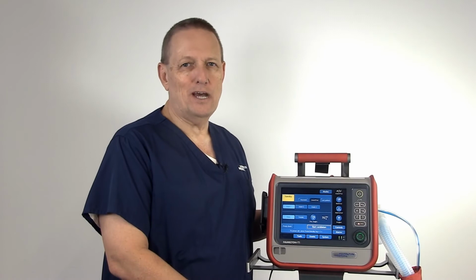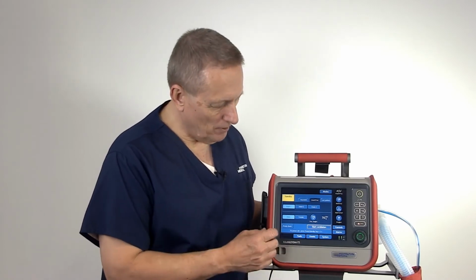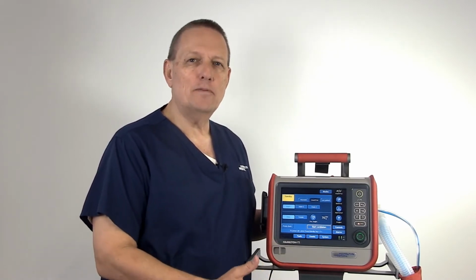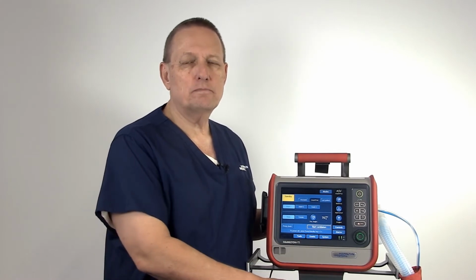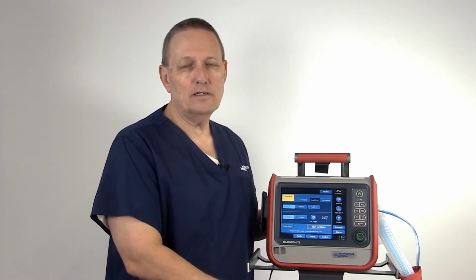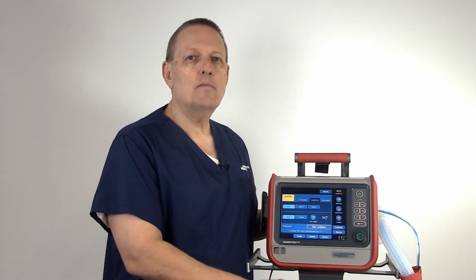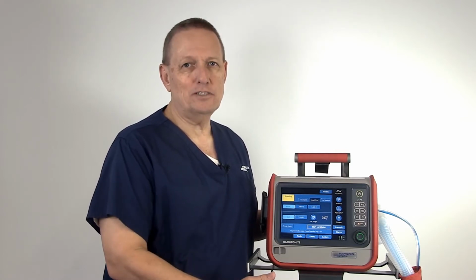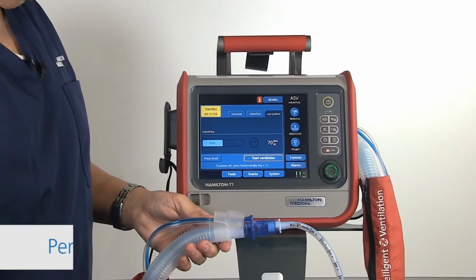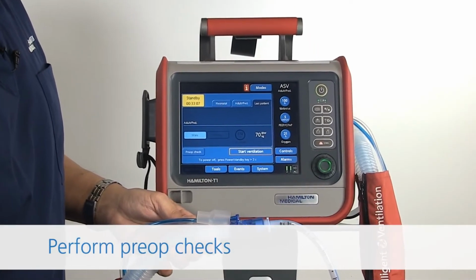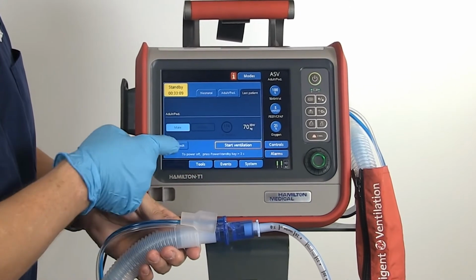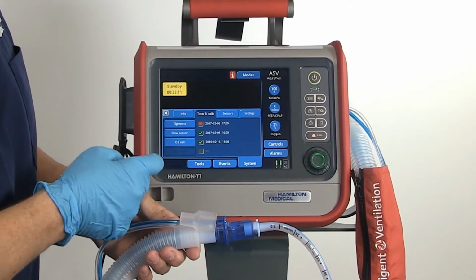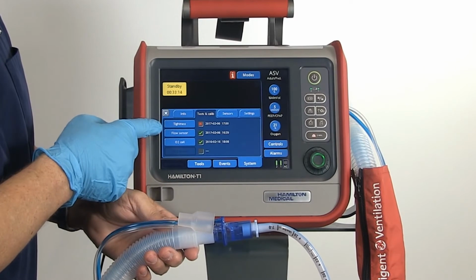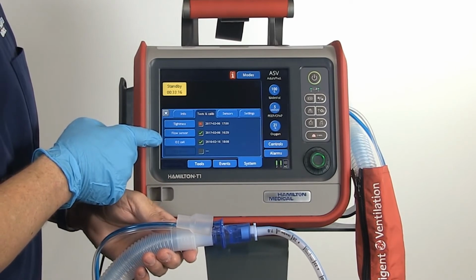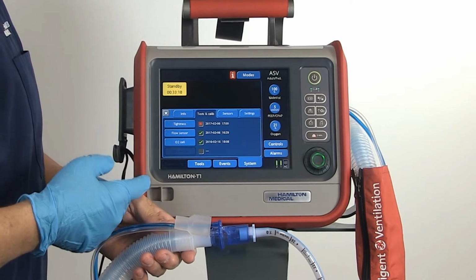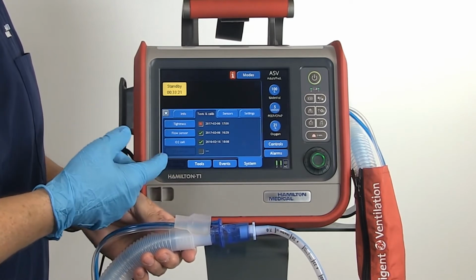You're ready to run the pre-op check. The pre-op check is a tab on the main screen. You run this pre-op check anytime you are placing a new circuit on the ventilator or anytime you're placing the vent on a new patient. Now we're ready to perform the pre-op check. At that point in time, we will press the pre-op tab and have our indications for tightness, flow sensor, and O2 cell. The O2 cell is only performed as indicated by the ventilator.